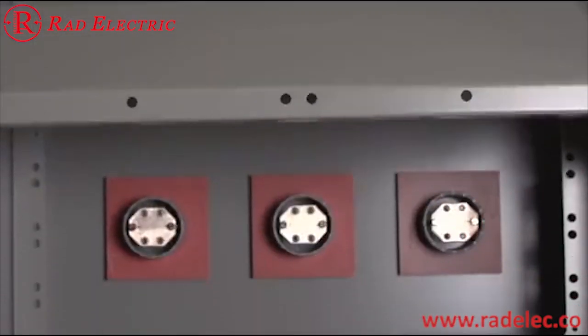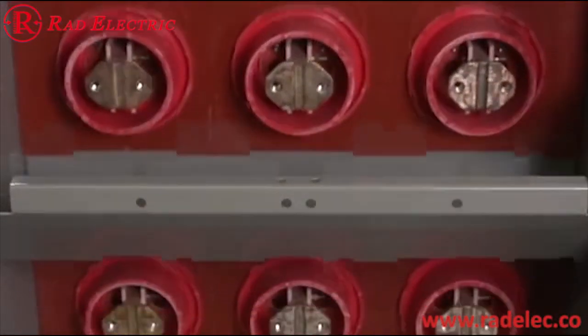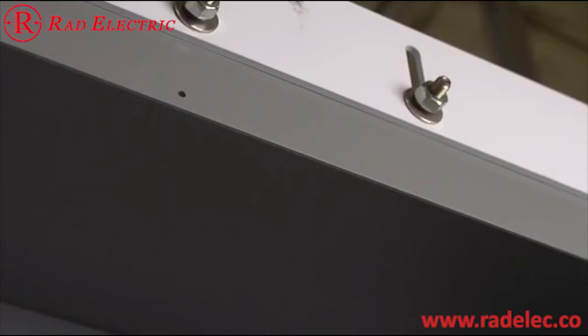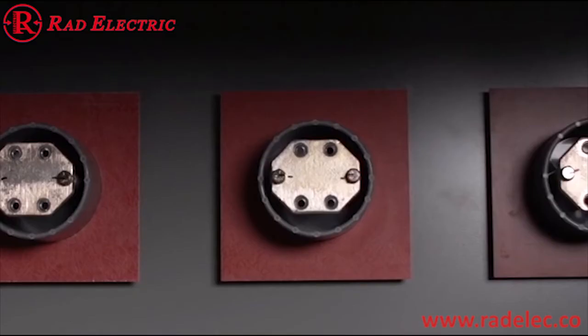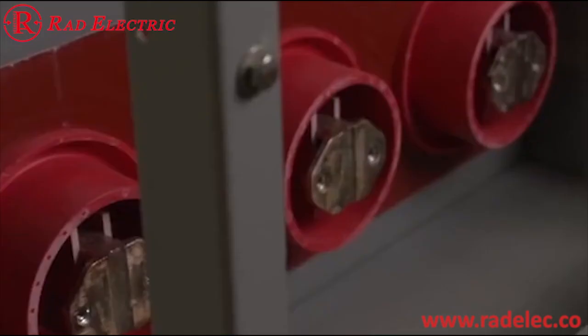Now, let's move to the rear of the GMSG skeleton. Starting at the top, you'll see this white lifting angle. This is a connection point for lifting purposes. Pass-through holes for secondary wires along the rear of the skeleton have a black round grommet that stays in the hole to protect wires as they're pulled through. Moving down to the D compartment, here are the bushings that provide a connection point to the primary bus bars. This big, open, rectangular space on the side of the skeleton is where the horizontal bus bars would be to connect one section to another.